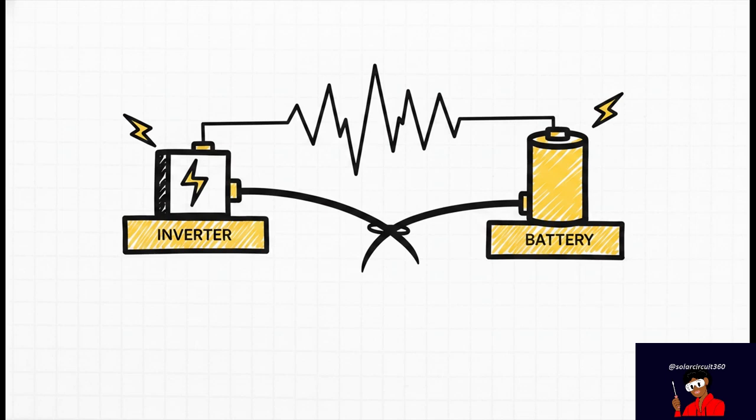And finally, the last of our unseen killers is a bad ground connection. All the devices on the network need to have a common reference point for what 0 volts is. If the grounds are at different levels, not only can it corrupt the data, but even worse, it can send a damaging jolt of electricity right through the communication ports, completely frying them for good.